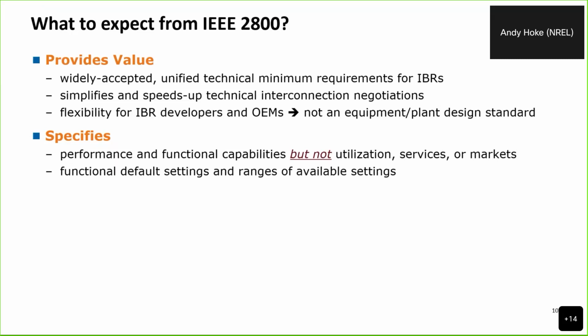For each of those capabilities, it provides different ranges of functional default settings and ranges of adjustability within those settings. It also specifies, once the plant is interconnected, what sort of monitoring needs to be placed on the plant. Do we need a digital fault recorder? Do we need a PMU, et cetera?